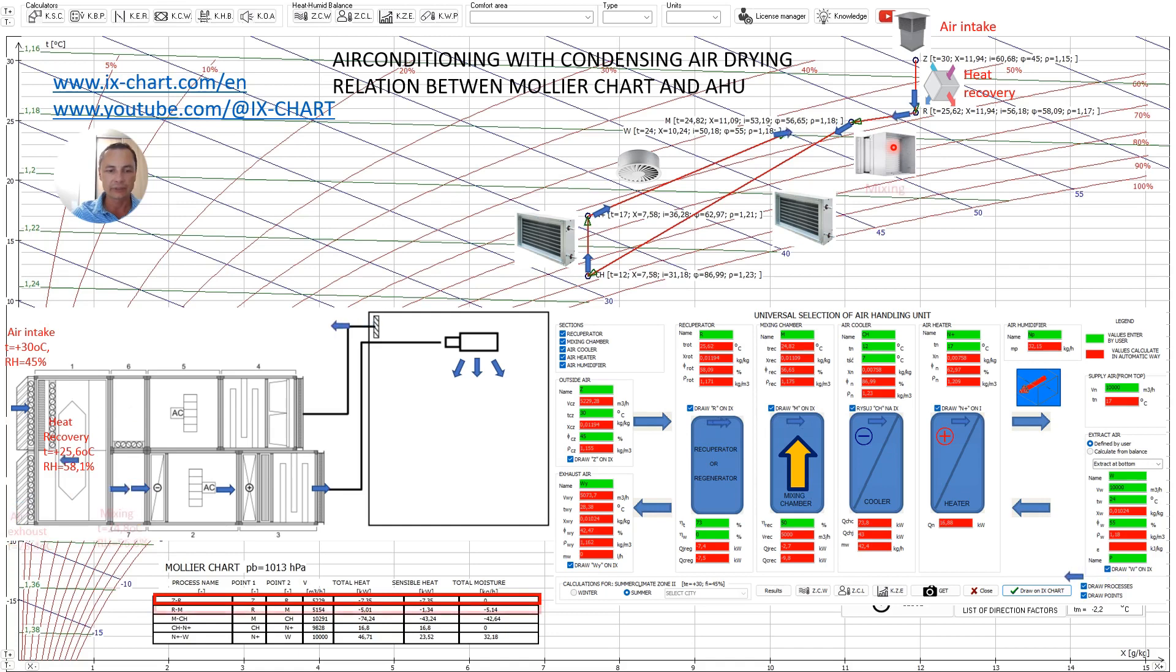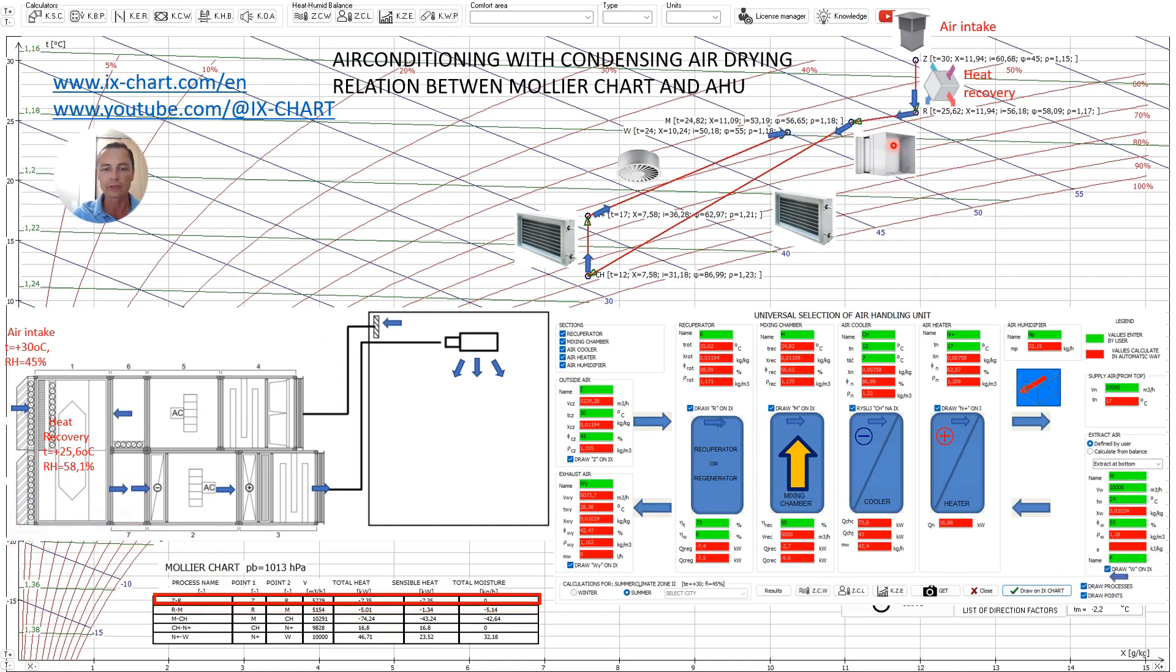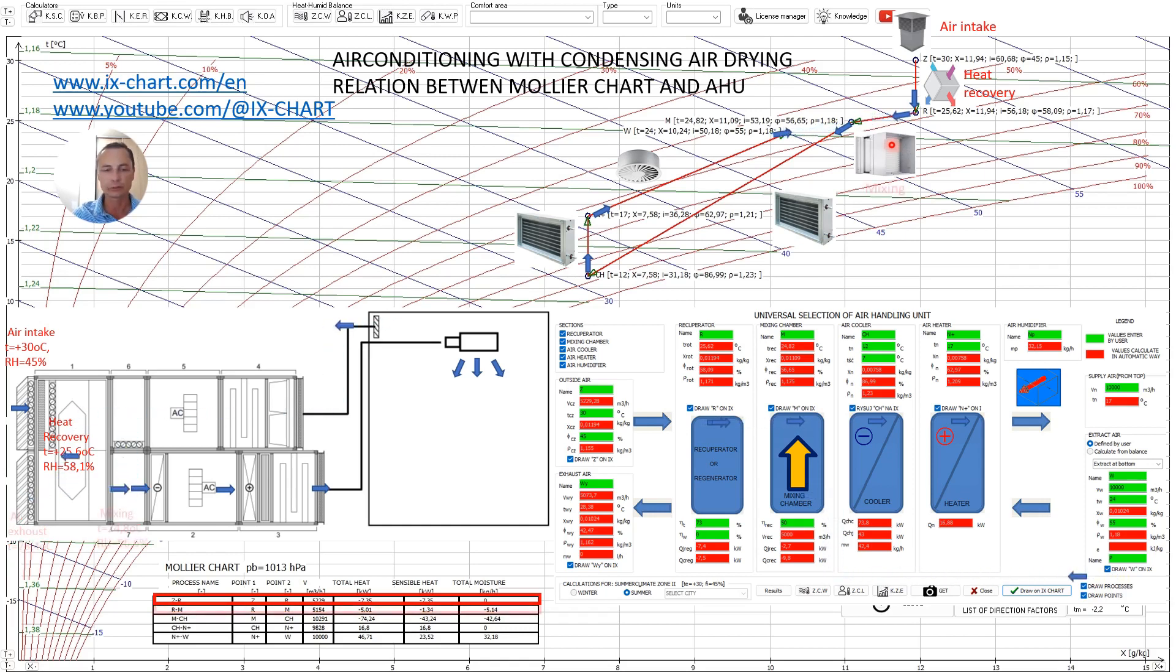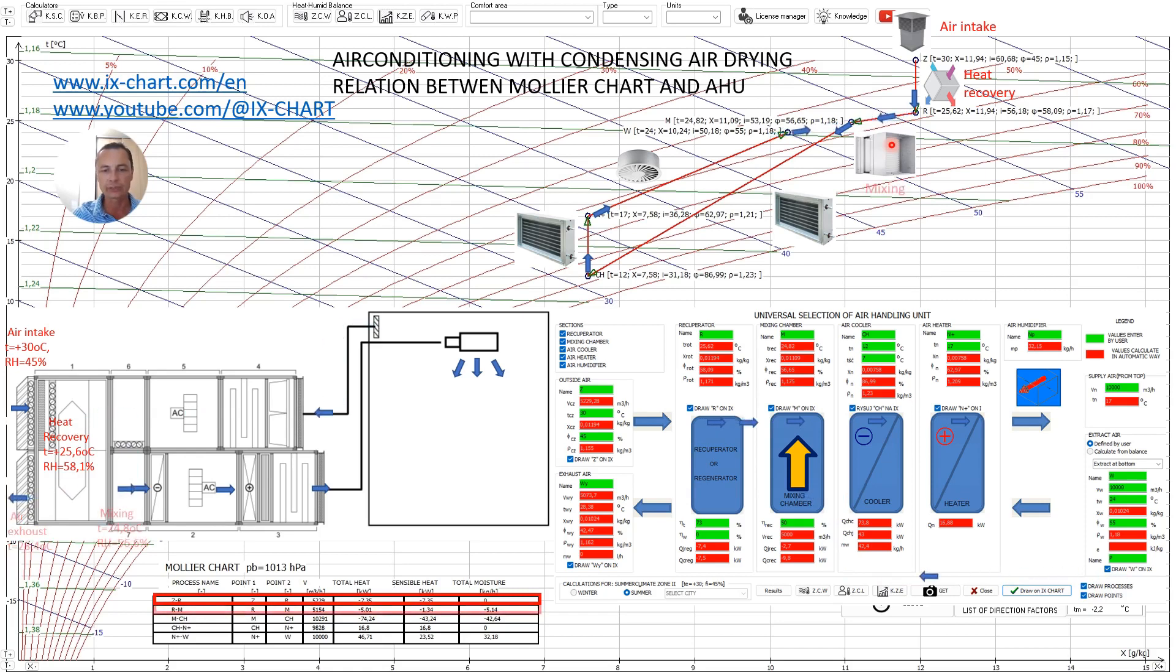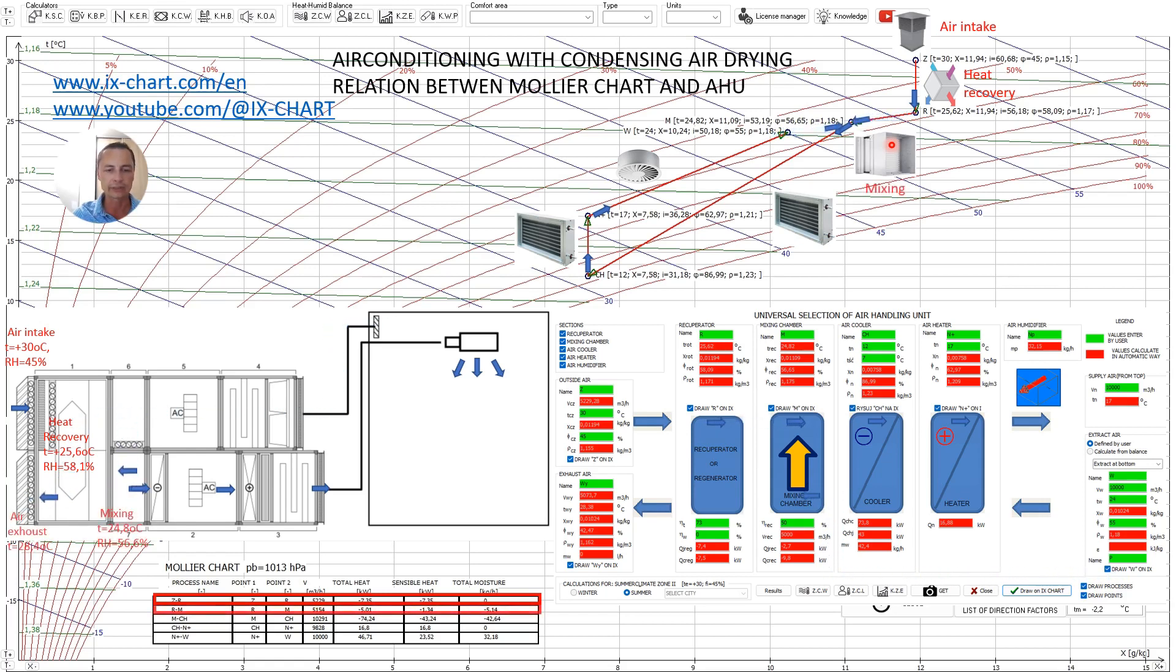In general the mixing chamber can be applied if the amount of air which is resulting from heat and moisture balance is greater than the amount of air needed for hygienic purposes and if there is no emission of harmful or pathogenic substances in the room. From an energy point of view the mixing chamber can be used if the enthalpy of the air after mixing is lower than the enthalpy of outside air after passing through the heat recovery unit.